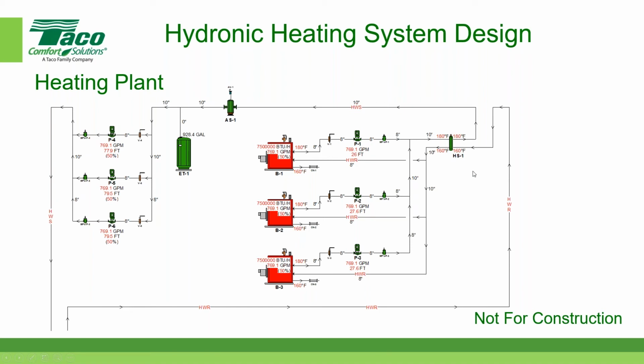So a hydraulic separator is a pre-engineered device that creates a bridge between the primary loop and the secondary loop. So if I was to draw just a piping system, this hydraulic separator takes the place of a piping system. So in other words, my primary piping might look like this, and there's my supply and my return on the primary side, and then I would come off here for the secondary side and then return back on the secondary side. So here on the left is the primary, and here on the right is the secondary. So that's if you did it with tees and pipes and so on and so forth.